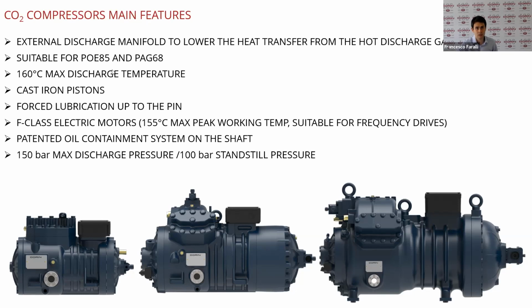We have cast iron pistons instead of aluminum ones, like for HFC. We have, for the models with oil pump, forced lubrication up to the piston pin. That is one of the most stressed parts in the compressor. All our motors are F-class insulated, meaning that they can work up to 155 maximum peak working temperature.